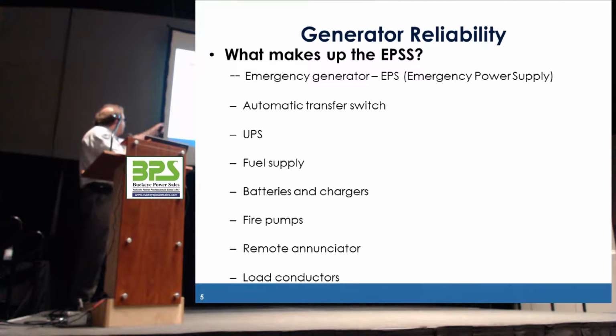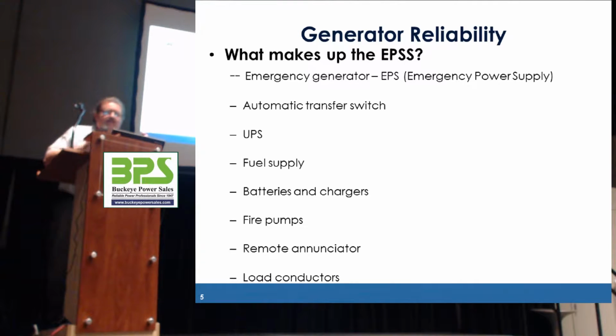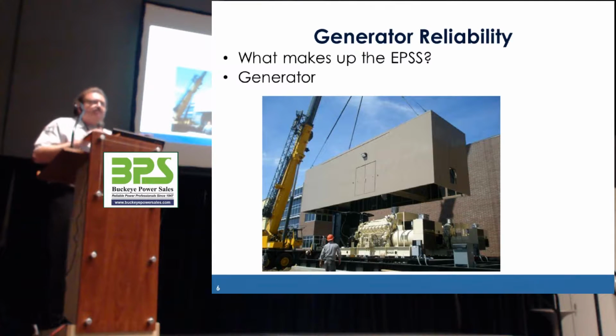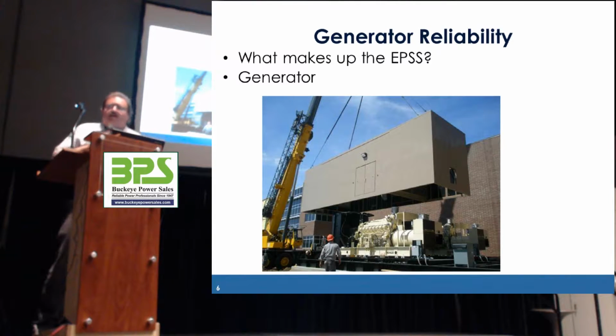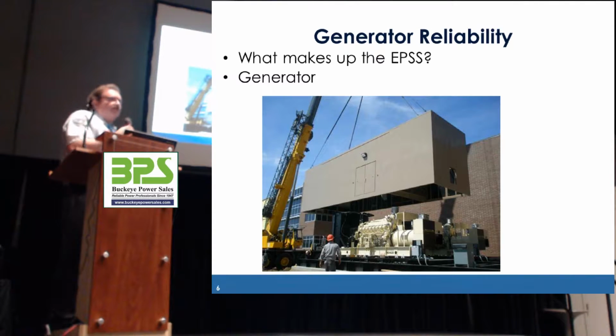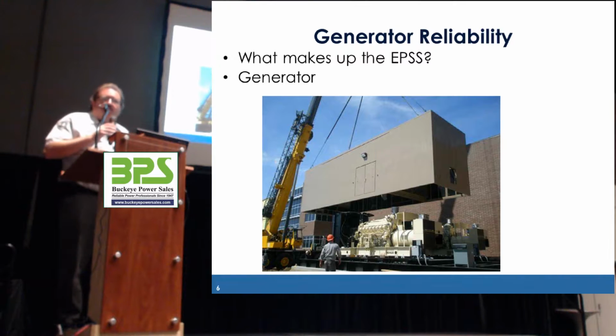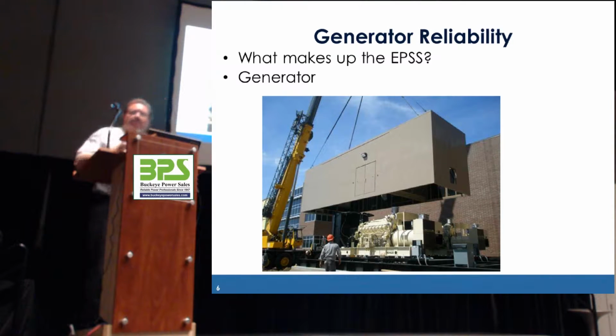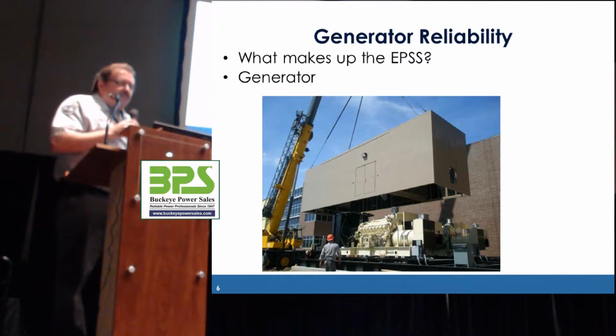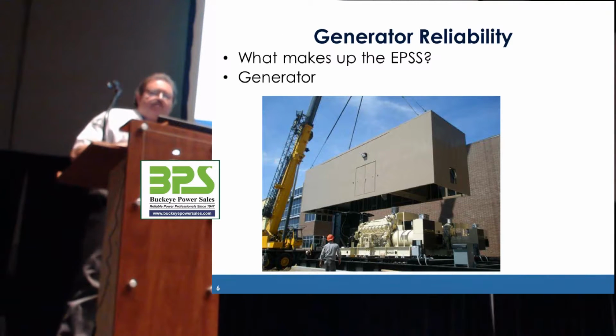Okay? So this is what makes up your supply: the generator, the transfer switch, the UPS, the fuel supply itself. You may have, we'll talk about that in a minute, batteries and chargers, fire pumps, and the load conductors themselves. And we'll discuss the maintenance requirements of those as we go. The generator can be, one generator can be a number of different generators. They can be indoors or outdoors. They can be in sound attenuated housings. They can be any number of combinations.